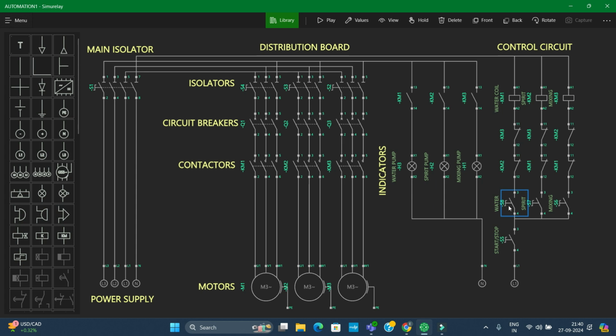Take an example: if I turn on this and this gets energized, the contactor for the mixing pump, the water pump is here and it is named KM1. So the KM1 contact has to be in both places. This means the KM1 normally closed contact is going to open. So even if I start this pump, there is no way I'm going to energize this one.